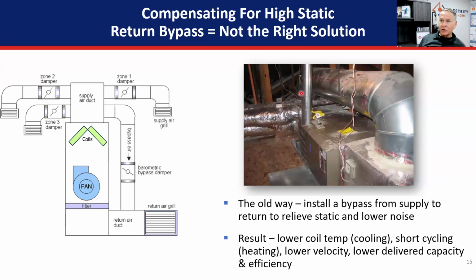And it's going to keep getting worse as it goes because I'm delivering all this hot air back into the plenum. This thing is just going to keep getting hotter and hotter. That means I could potentially be blowing air down these ducts that's 130, 140, 150 degrees, and that's going to cause the limit switch in the furnace to open. Limit switches in furnaces will open, cool down, and close again, until they don't. Then you get that call: it's blowing cold air. We go out, we don't understand why the limit switch is bad. We can just say, we got a bad limit switch. It's a bad part. But limit switches don't go bad, they just don't stop open.